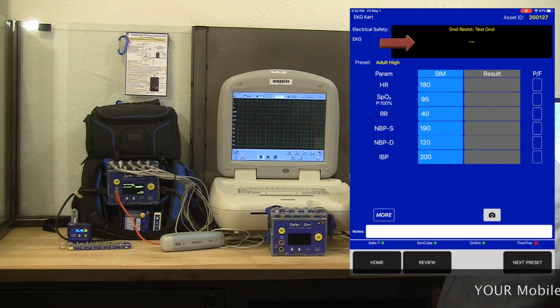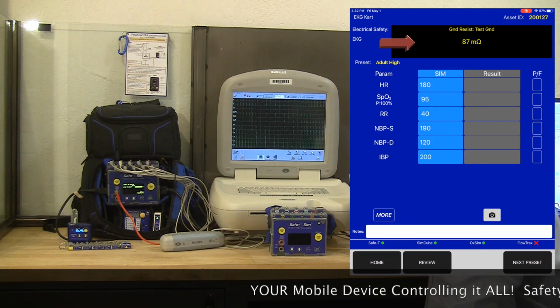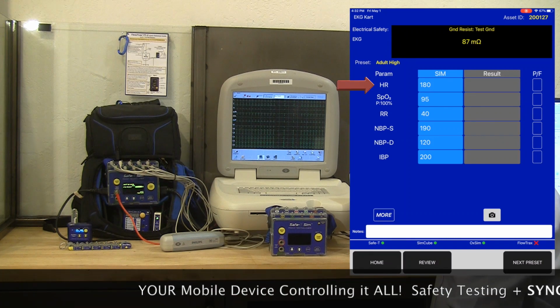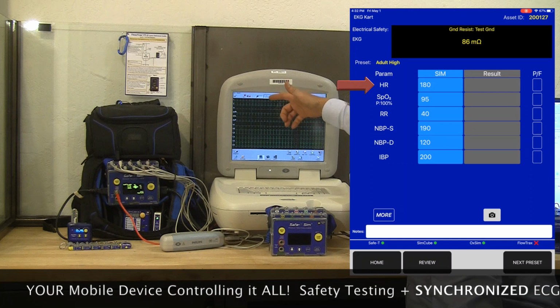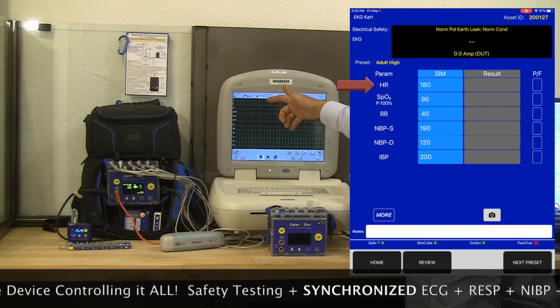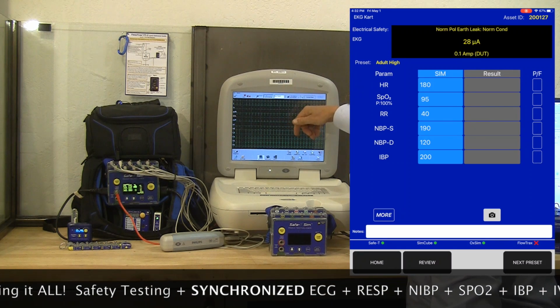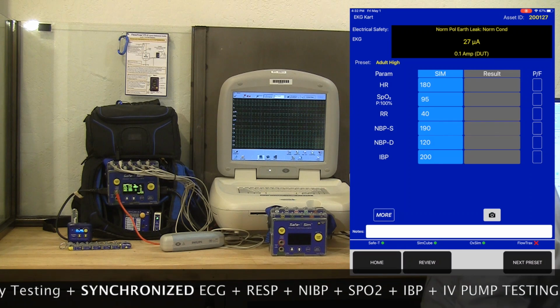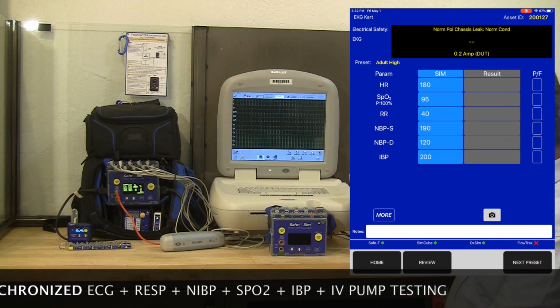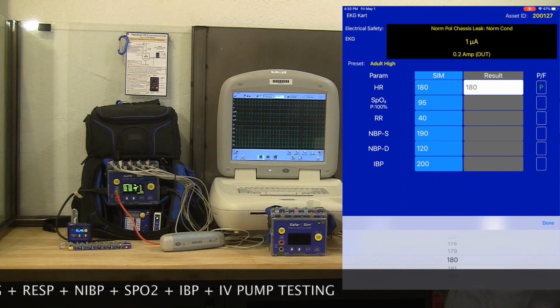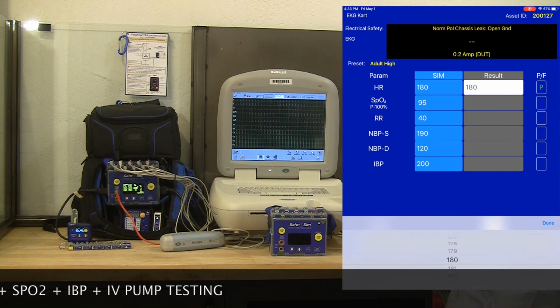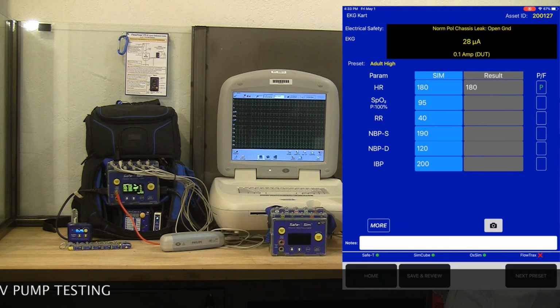So the electrical safety testing is running, and I've got my simulations already pre-programmed. It starts at 180 beats per minute, and I can see that the heart rate averaging on here is already catching up. It takes about 10 seconds, and it's reading 180. So I've got a simulation of 180. I tap the results column. It immediately pops to the target simulation and starts at pass. If it's a fail, I can change it.